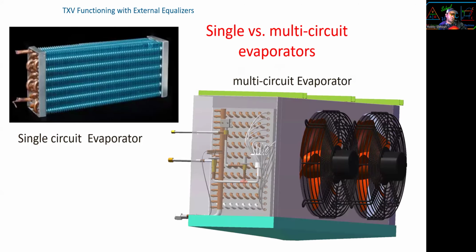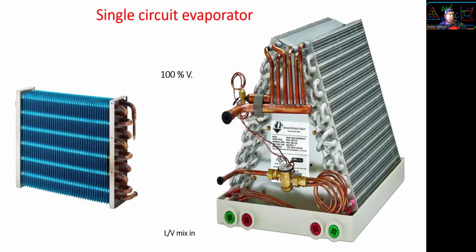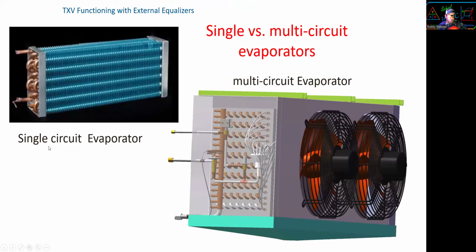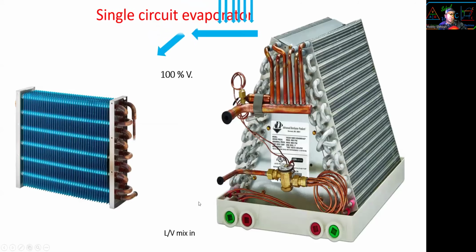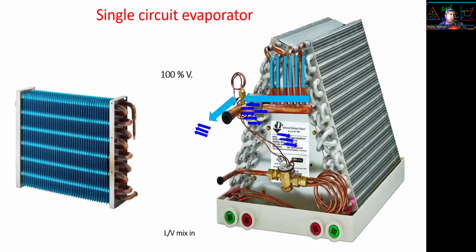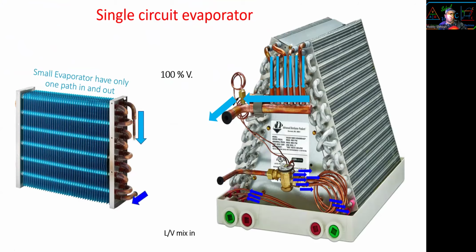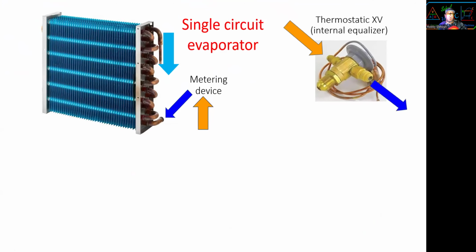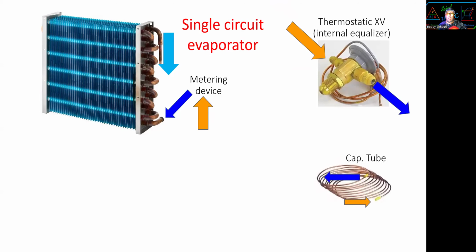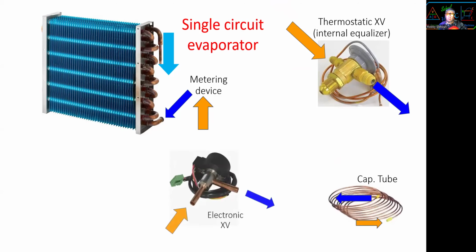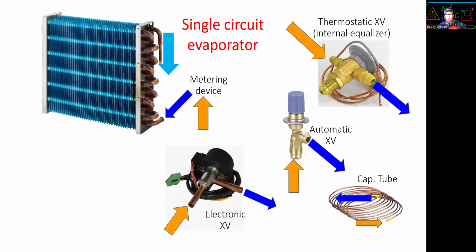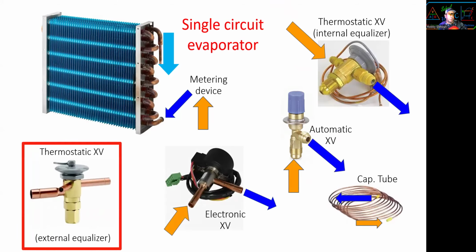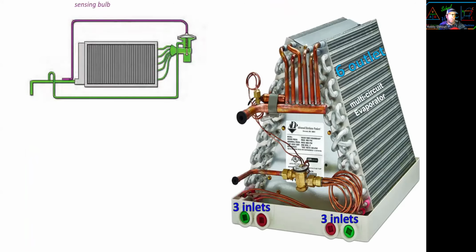Now, single circuit evaporator versus multi-circuit evaporator. Single circuit, only one way in, one way out. Multi-circuit evaporator, as you can see, we have 6 ways in and 6 ways out. A small evaporator has only one way in, one way out. On a single circuit evaporator, we can use thermostatic with internal equalizer, a cap tube, an electronic, an automatic, a piston, I guess, but we cannot use an external equalizer. It will not work.